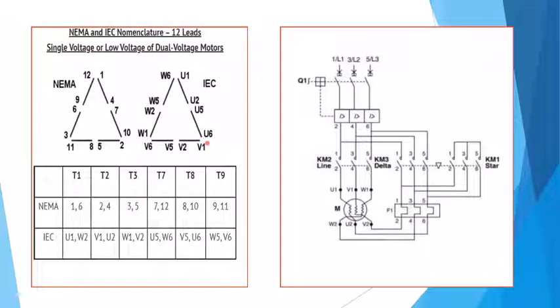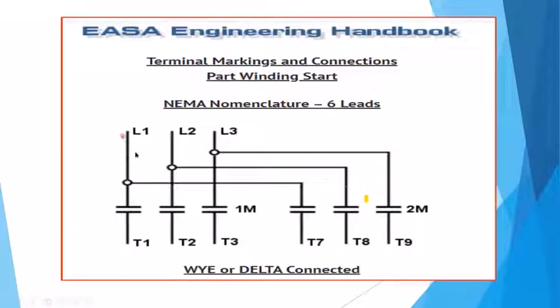They also had auto transformer starters, all kinds of things out there to eliminate that inrush. The issue is that for some applications, if you did the part winding start type starter, what would happen is the motor sometimes wouldn't have enough torque. So if you had a fairly high torque application, it would really reduce the torque and not produce enough.